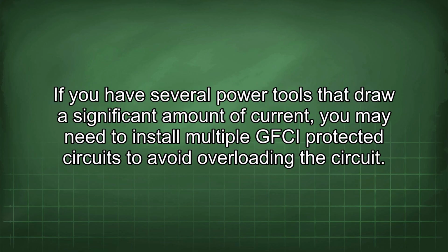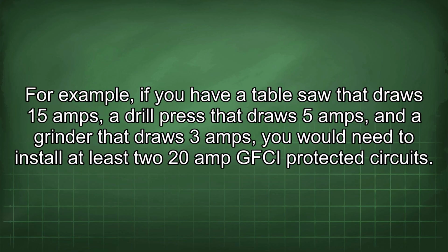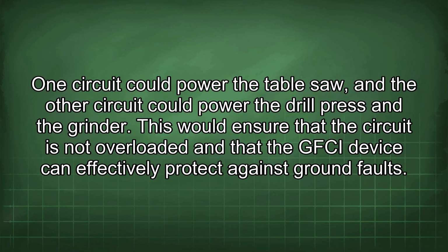If you have several power tools that draw a significant amount of current, you may need to install multiple GFCI protected circuits to avoid overloading the circuit. For example, if you have a table saw that draws 15 amps, a drill press that draws 5 amps, and a grinder that draws 3 amps, you would need to install at least two 20 amp GFCI protected circuits. One circuit could power the table saw, and the other circuit could power the drill press and the grinder. This would ensure that the circuit is not overloaded and that the GFCI device can effectively protect against ground faults.